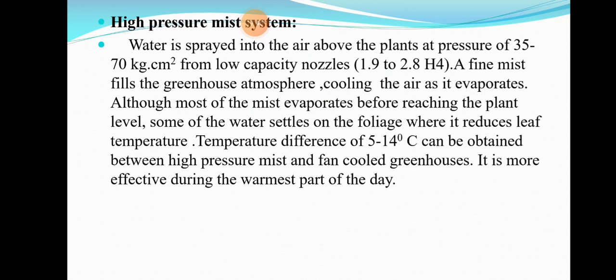A fine mist fills the greenhouse atmosphere, cooling the air as it evaporates. Although most of the mist evaporates before reaching plant level, some water settles on the foliage where it reduces leaf temperature. A temperature difference of 5 to 14 degrees centigrade can be obtained between a high pressure mist and a fan-cooled greenhouse. It is more effective during the warmest part of the day.